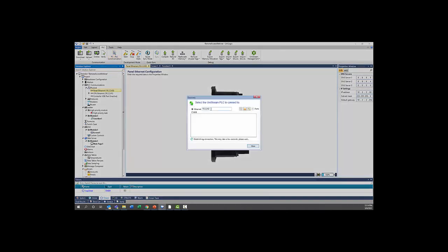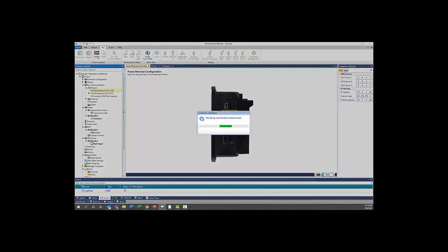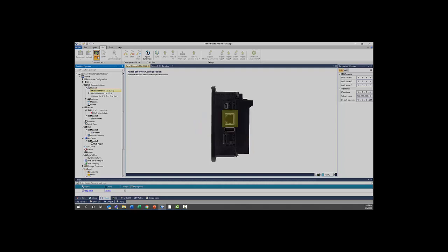The connection that you see here is also the connection that will be used when you go to download to the PLC. Alright, and again, you'll see that green check when you have connection to your PLC. The most basic form of remote connection that you'll be able to use is this online mode here, where you'll use those communication settings that we set up in the PC, PLC communication. You can press this online mode here. And then it will connect to your unit, and it will validate the password. A PLC password is something that you can set up to the PLC when you download the project to the PLC. It will give you the option to keep the default password, or you can change it to a password that you would like it to be. And this password will be required for all communication to the PLC.